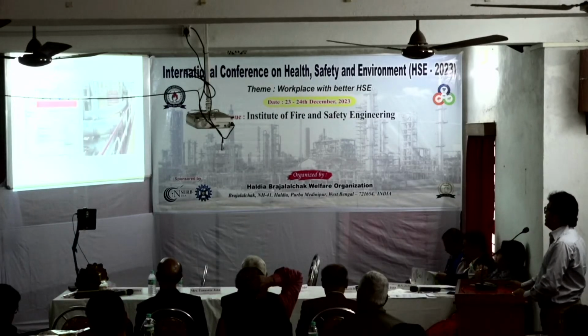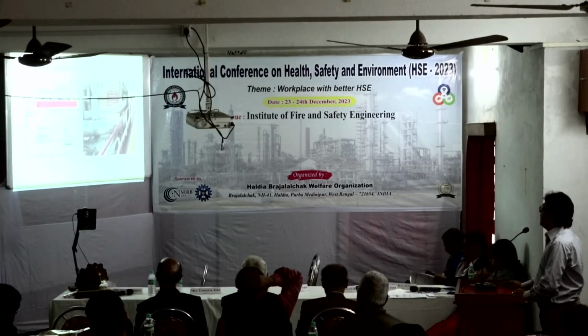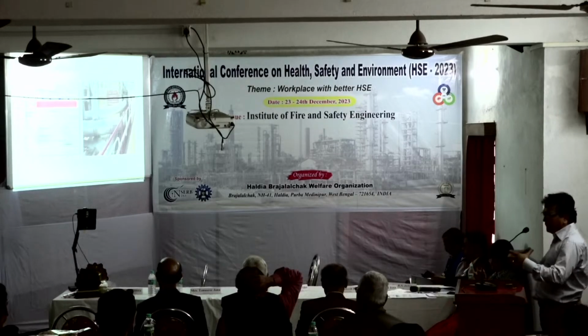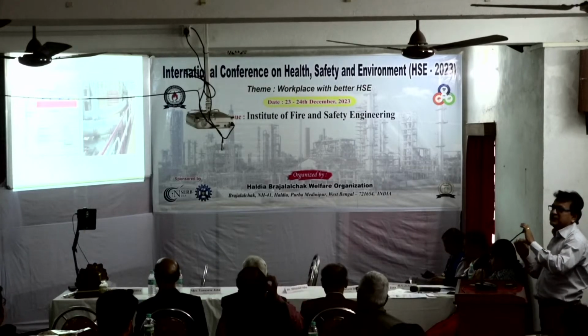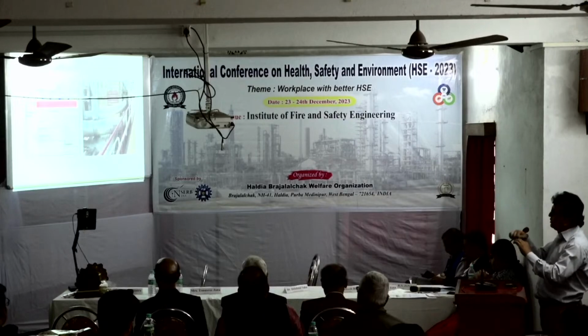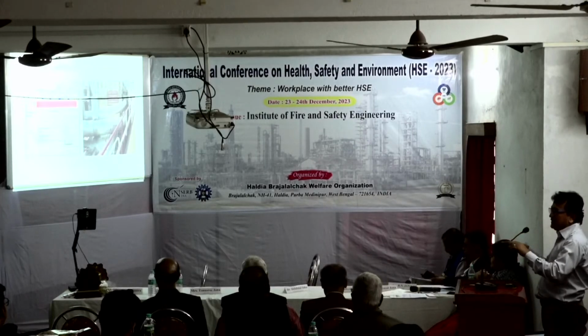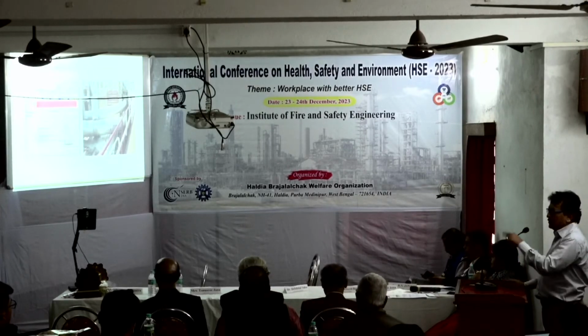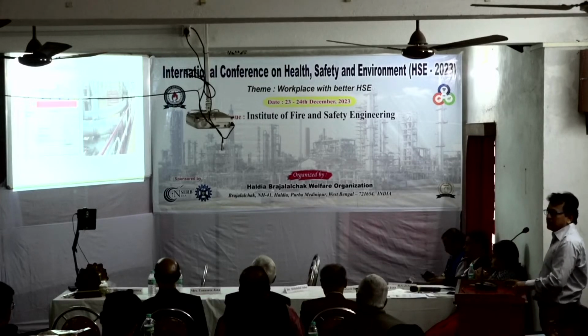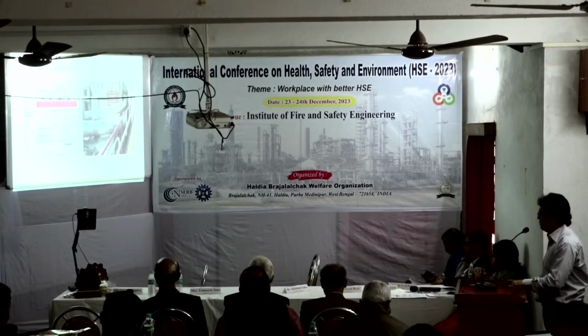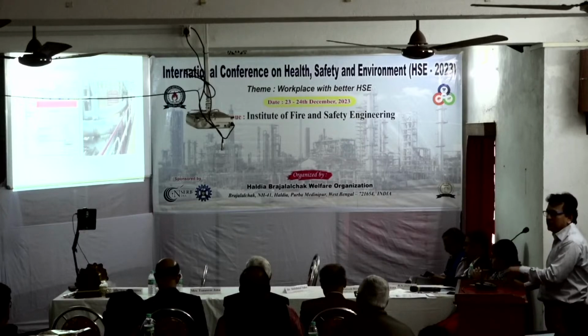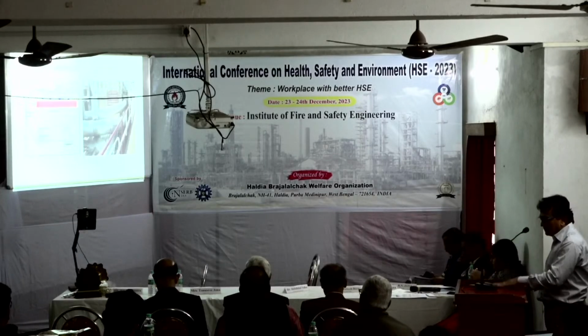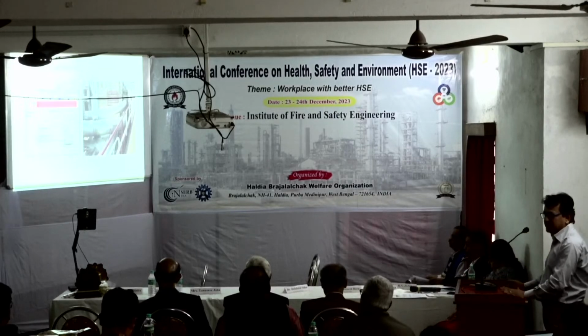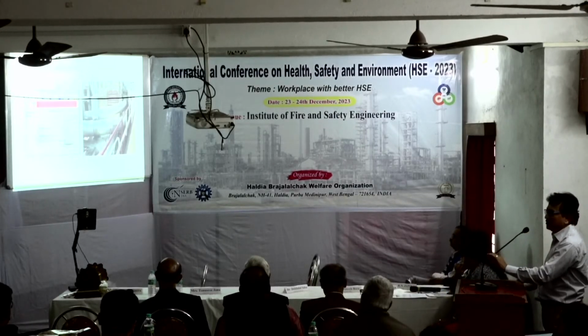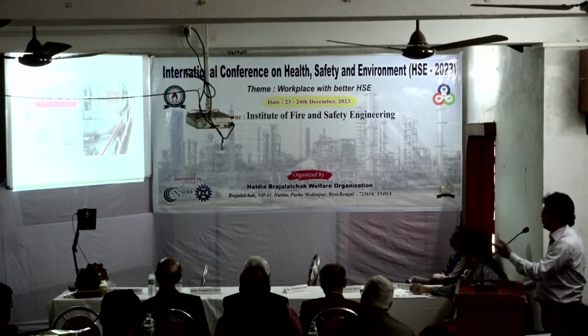So this is the pipeline; we mount some sensors on it. There is a pipeline with a 6 inch insulation outside it, and our sensors are mounted inside this insulation at 1 meter intervals in a zigzag pattern. If a catastrophic failure occurs inside this tube, our sensor suddenly senses the moisture, because the pressure inside is 10 bar while outside is 1 bar, so condensation takes place easily in our sensors, and the signal goes to the control room.